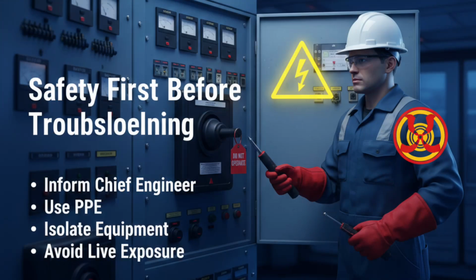Now let's begin. Safety before troubleshooting. Before touching any switchboard panel, safety must always be your first priority. On the screen, you can see a marine engineer wearing proper PPE, insulated gloves, helmet, and using proper tools. This is not optional. Switchboards operate at high voltage and high current. One mistake can cause serious injury. Always inform the chief engineer before starting troubleshooting. If required, follow permit to work procedures.